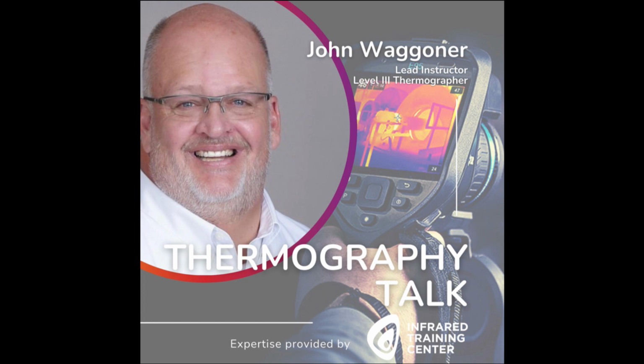Remember that training is to help the qualified person determine what's energized inside an enclosure and what is not. A qualified person is to be able to know and identify the nominal voltage within that unit, 50 volts and up, and also what are the approach distances for safety for both electric shock and electric arc flash.